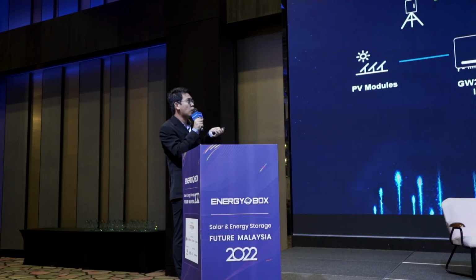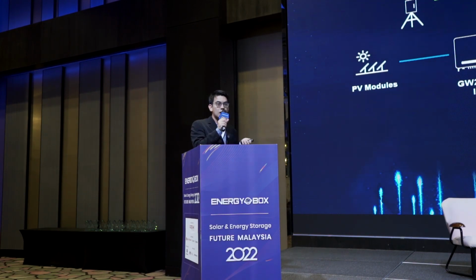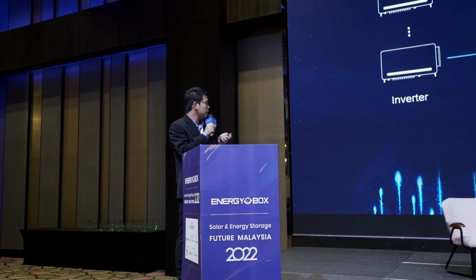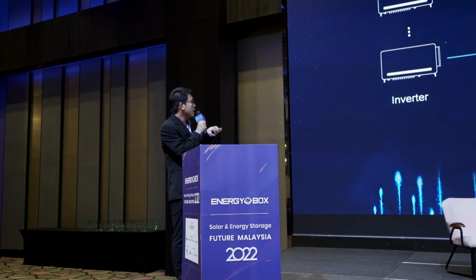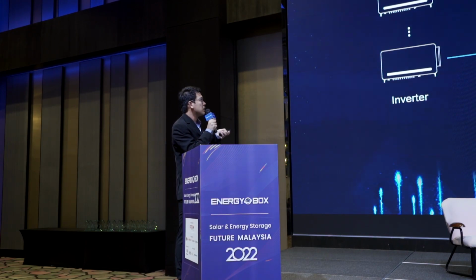We have a data logger called the SCB3000B, where you can connect with PLCs and monitor the MV station, as well as communicate through fiber optic with all the PPCs and SCADA. GoodWe also provides a remote monitoring platform or a local monitoring platform, SolarOS, specially customized for utilities monitoring solutions. As you can see, there are inverters connected to the LV side of the MV station at 800 volts. We can connect more than 26 units, or 28 units to be exact.